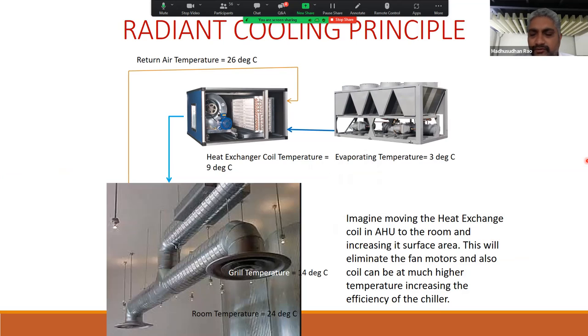I want to explain radiant cooling in a way that all of you are familiar with. So that is why I usually add this slide. This is something we are all aware of, right? A chiller produces chilled water. Now chilled water goes into the heat exchanger in the AHU, and we have hot return air coming back at maybe 26. The heat transfer happens in less than a second in the heat exchanger, where 26 degrees air becomes maybe 14 or 16 degrees air, and then it is pumped through.